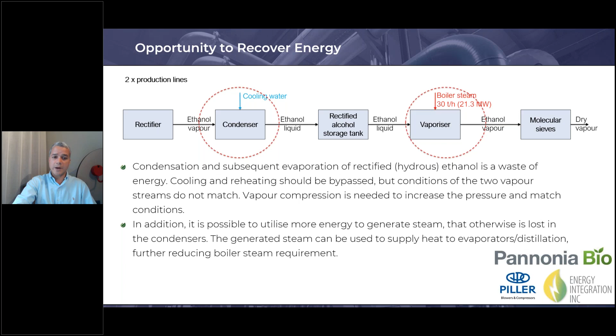We have all the bypass here. This is ethanol vapor from top of the rectifier at 340 millibars. This is the installed MVR series with the reboilers. We put 5.9 megawatts of electricity, and then we get the alcohol vapor at the right pressure and temperature to feed the molecular sieve. We also condense some of the alcohol vapor to generate 16.6 tons per hour of steam, equivalent to 11.8 megawatts of natural gas.